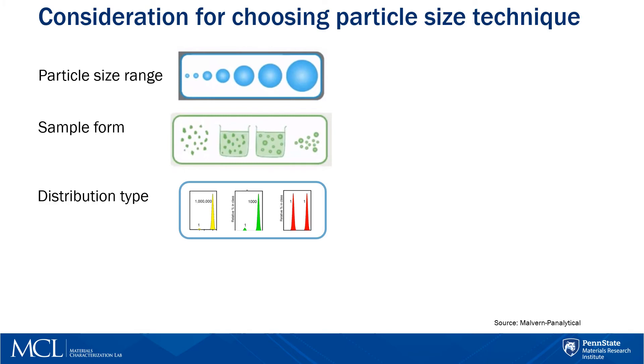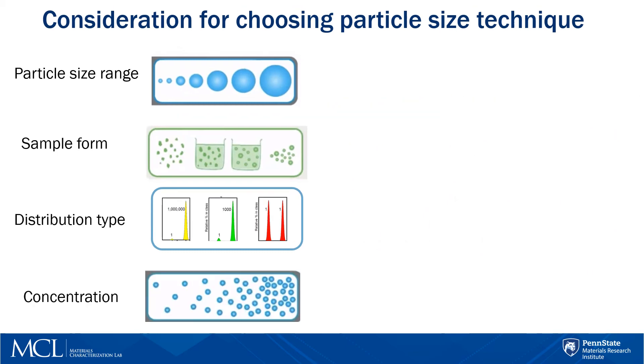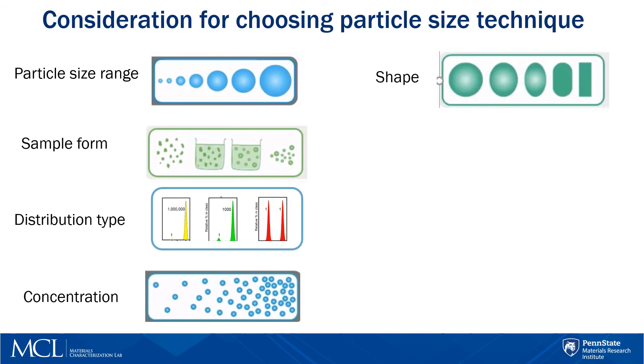Another important criterion is the size distribution type. Each technique has its preferred way to present the distribution: intensity-weighted for dynamic light scattering, volume-weighted for laser diffraction, and number-weighted for automated imaging. Here you see a size distribution for a sample that has the same number of 5 nm and 50 nm particles. Note that the intensity and volume distributions are biased towards larger particles and agglomerates. Shape is also a consideration — some equivalent sphere models may not work well for particles with irregular shapes.